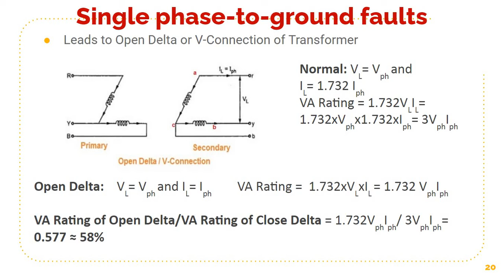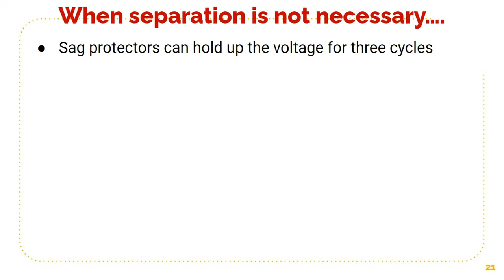So if there is an open delta here, then this type of connection, that is delta V connection, will ensure that the output voltage does not go below 58%. Now if you employ a sag protector, sag protectors are expensive, but they can hold voltage for a maximum of 3 cycles. So a combination of electronic sag correctors and high speed relaying, 3 cycle relaying, should satisfy the SEMI F47 requirements for rapid fault clearance.